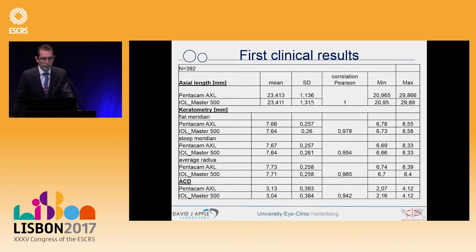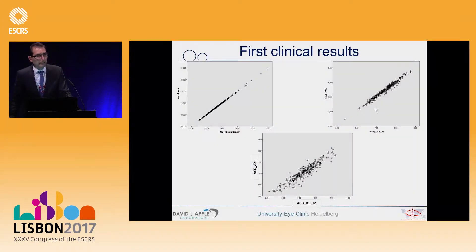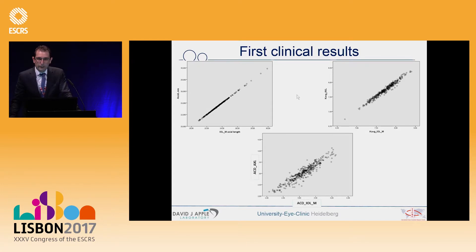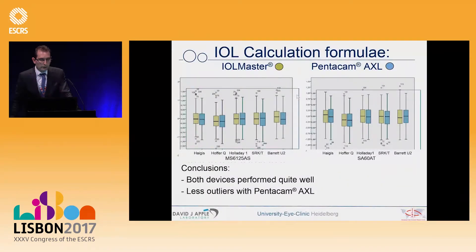The correlation between the two devices is nearly perfect. With regard to keratometry values — the flat and steep meridian and the average radii — there is still a very high correlation between the two devices across the whole group. Anterior chamber depth measurements also correlate very well. In the scatter plots for axial length, K-values on average, and anterior chamber depth, the regression lines remain in the same quadrant, confirming high reliability for both devices.